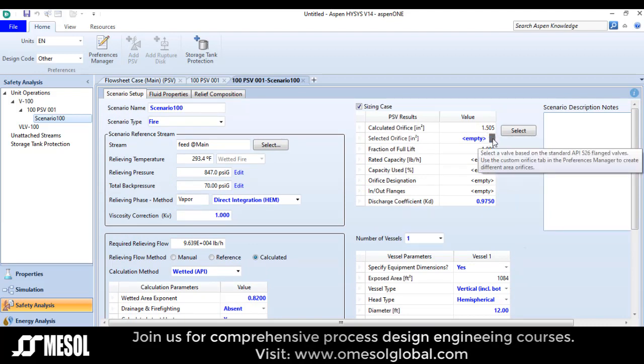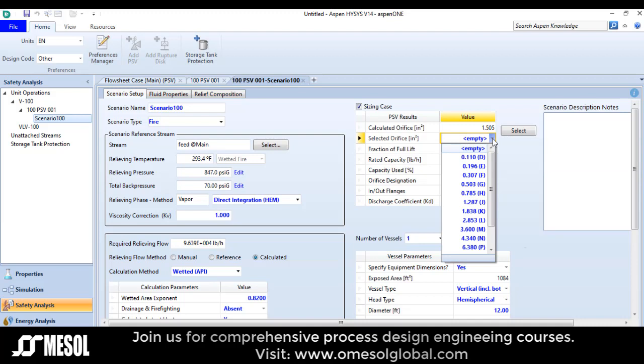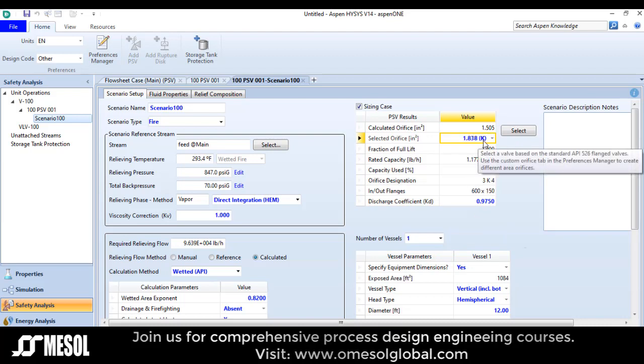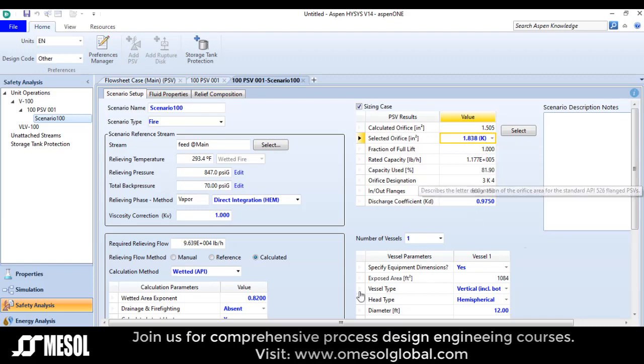The calculated orifice size is 1.5. I will select an equivalent or higher size. The next available is 1.838, designation K. So the designation of the orifice is K, and you can see that the orifice calculation is completed.